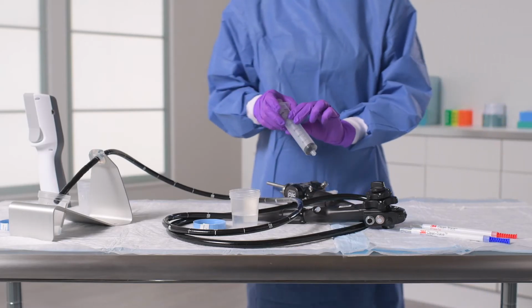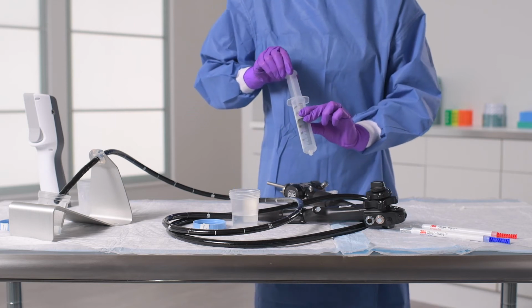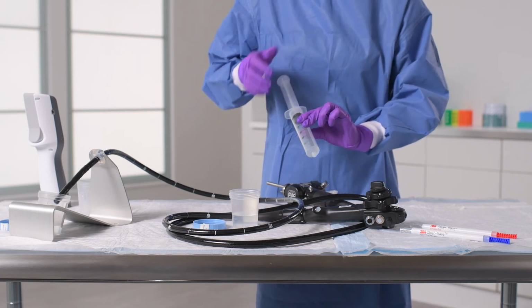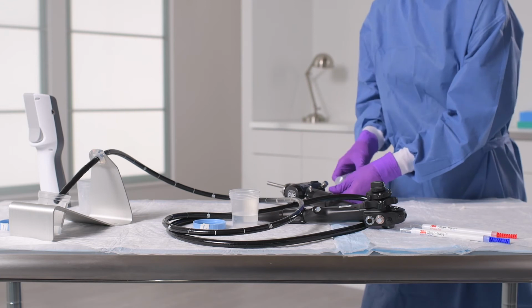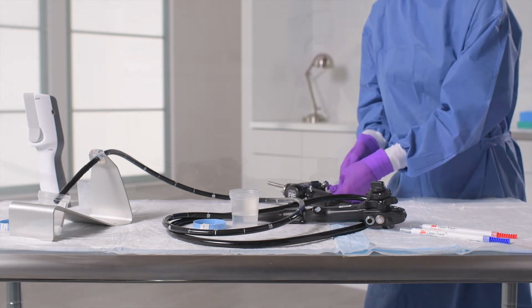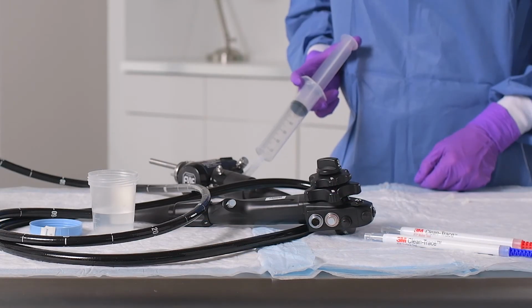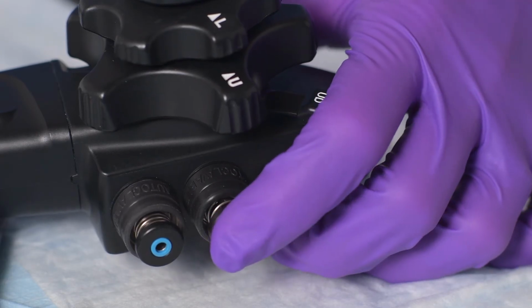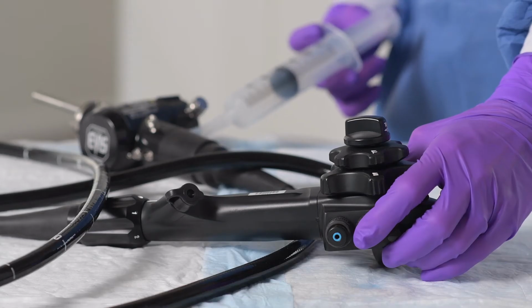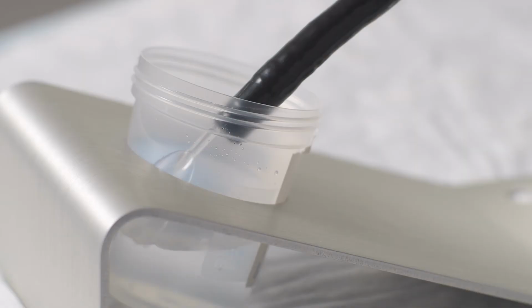Detach the syringe from the connector and draw in 60 cc's of air. Then reattach to the connector. If using the plug, press down on the syringe to push air through the endoscope. Otherwise, press down on the suction valve while pressing down on the syringe. This air flush will push any rinsate remaining inside the endoscope into the collection container.